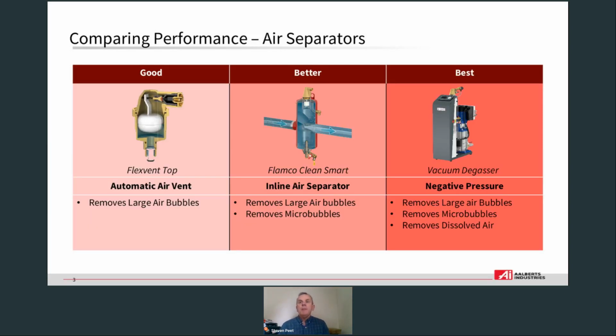So there are a variety of methods for removing air. We'll start with air and improving our water quality. There are automatic air vents, inline air separators and vacuum degassers. One of the major problems in systems is dissolved air in the water. Water by its nature absorbs gases easily until it becomes saturated, and that saturation depends on the pressure and temperature of the system. At low pressures, less gas can be absorbed.